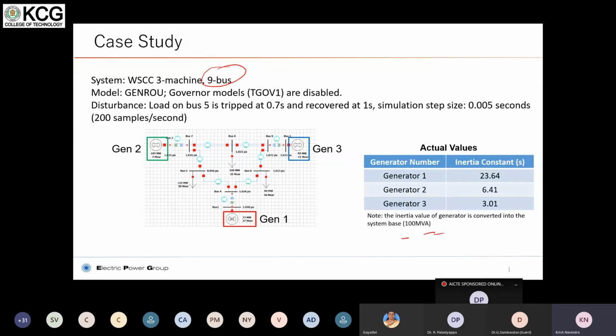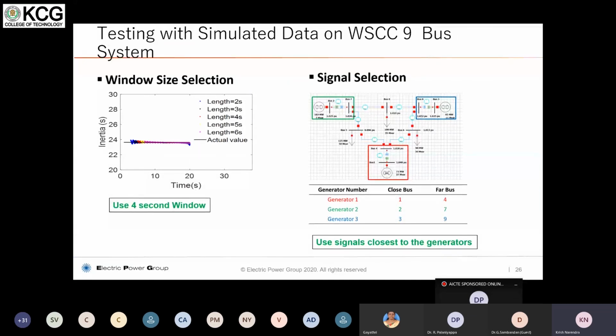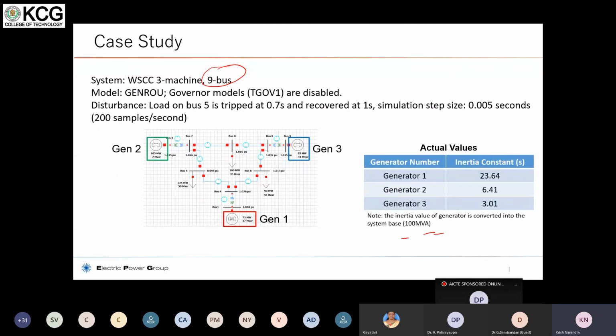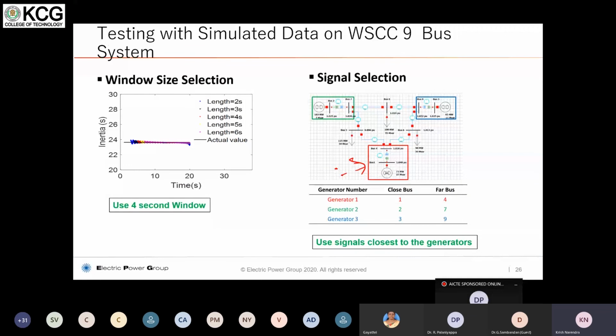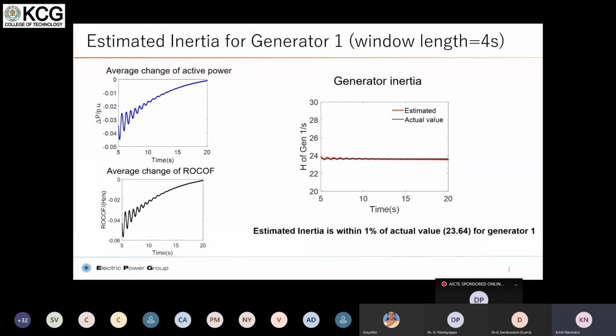Now, with this method, what we have calculated is the inertia constant of generator 1 of the system, which is close to 24. We have obtained our results very close, with very good accuracy, using a 4-second time window. Basically, that means you set a 4-second time window, evaluate the dynamic equation, and move the window for every sample of the synchrophasor data, depending on the sample rate of the synchrophasor data, and then evaluate the value of H. That's what we have done. If you look at the estimation of inertia with a window length of 4 seconds, and look at the average power and the variation of average ROCOF, this divided by this essentially will give you the value of H multiplied by the system frequency, as shown. You can see that the value will converge very nicely over a period of time.